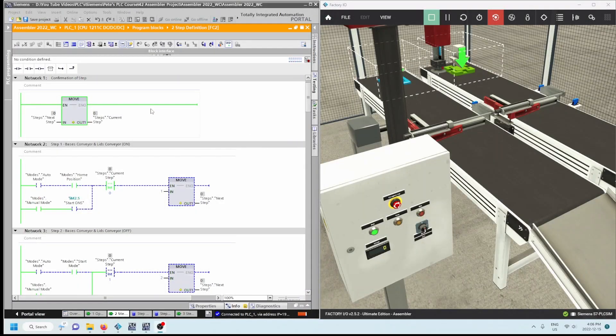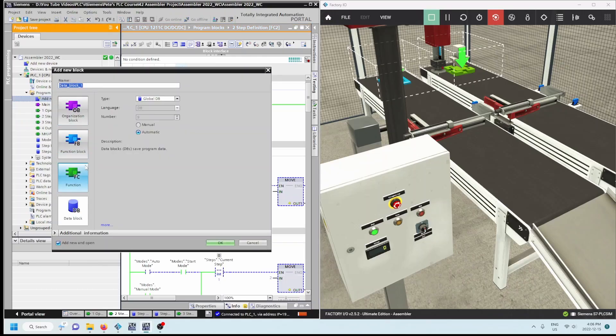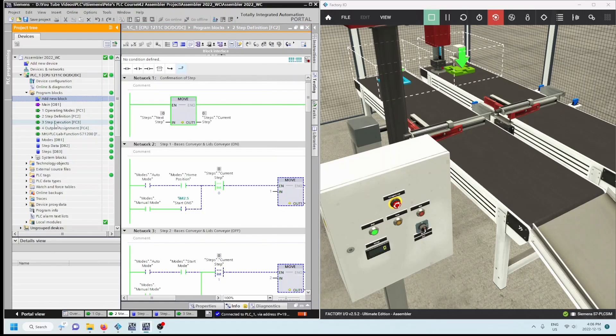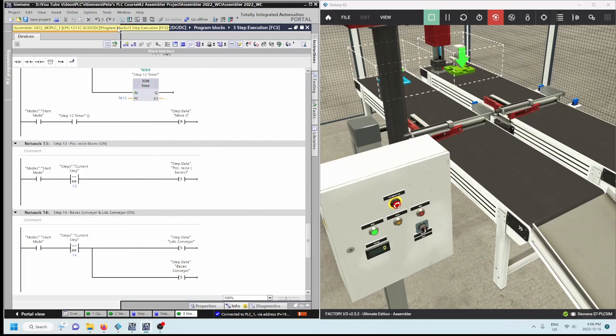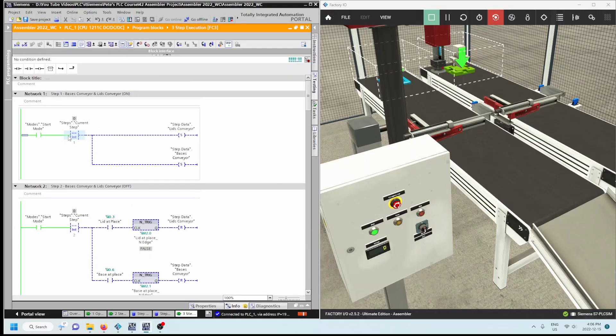We're almost there — step definitions are done, so next we need step execution. We've got another function here; remember for any of these we're adding a new block, adding a function, and this one is called step execution. Scrolling to the top: in the first network, bases conveyors and lid conveyors are going to be on. They were in manual mode here. Let's press the start push button — currently we're in step zero. If current step equals one, then set the lids conveyor and set the bases conveyor.